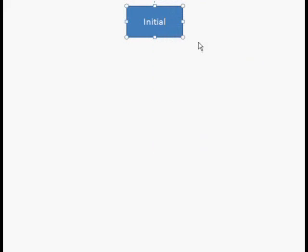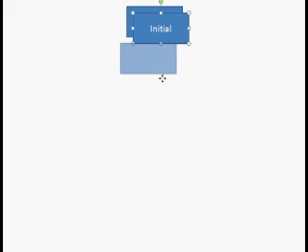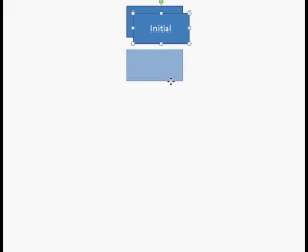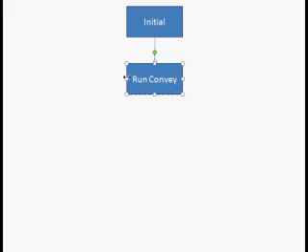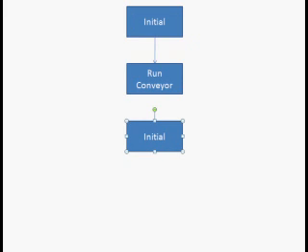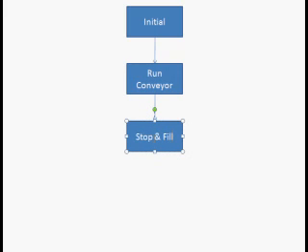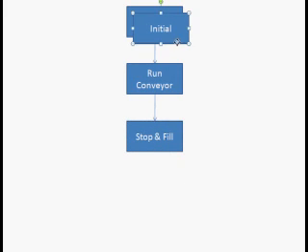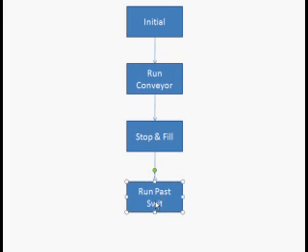The first block I'm going to draw is the initial state and this represents the power-up state. After we're powered up we're going to press the start button and that takes us into the next step which we are going to call run conveyor. At this point we want the conveyor to run until the box makes it to the prox switch. After the box makes it to the prox switch we're going to stop and fill the box and after the box is full we're then going to run the conveyor until the box passes the prox switch and at that point it will go back to run the conveyor again.